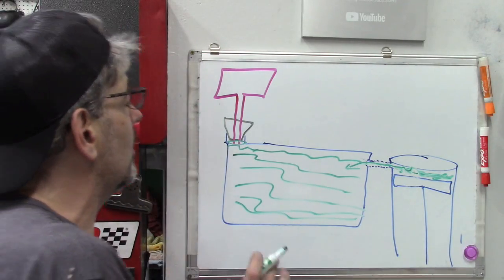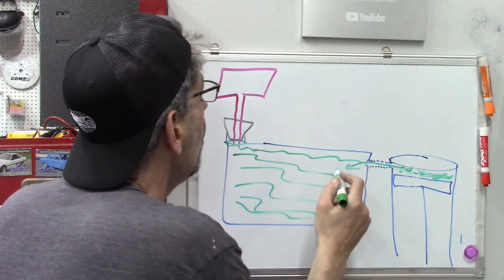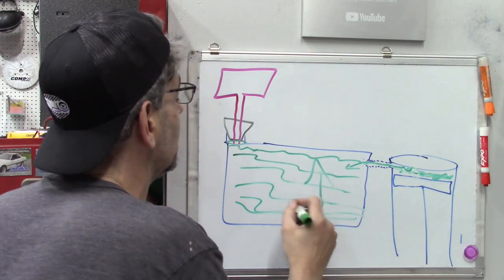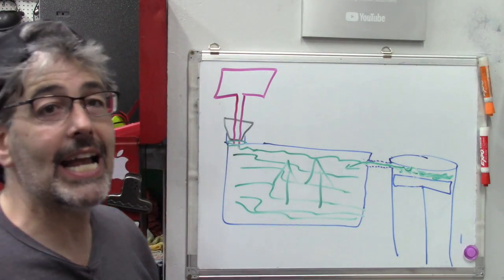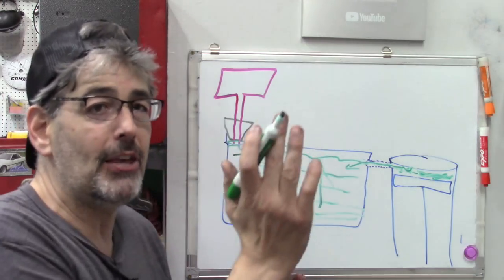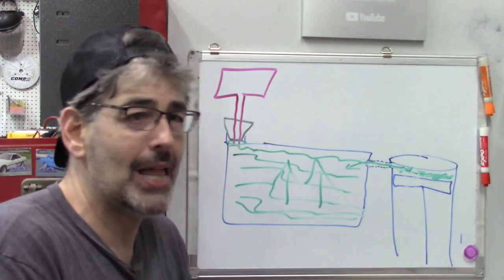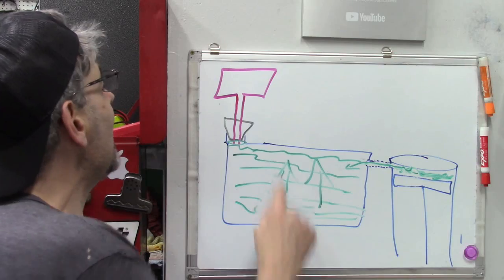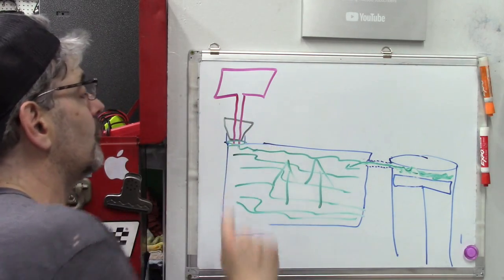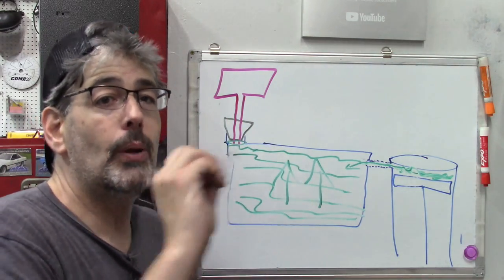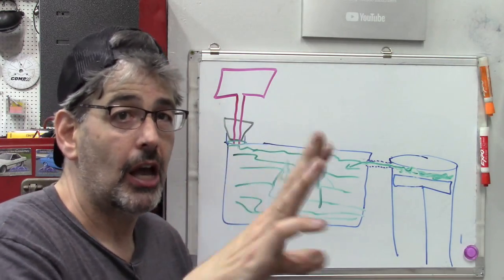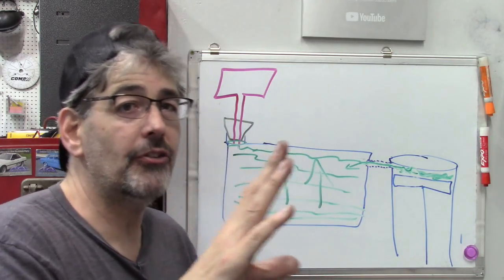The point is that we would build up pressure in this radiator with every time that piston is trying to push that liquid back. And if we have the pressure transducer on the radiator neck, we would see those pulses of pressure pretty consistently.